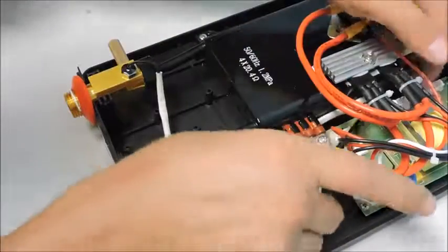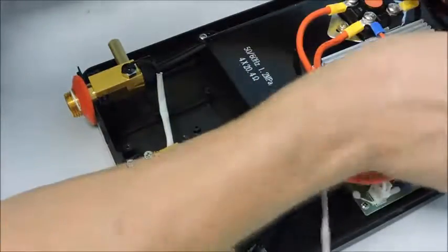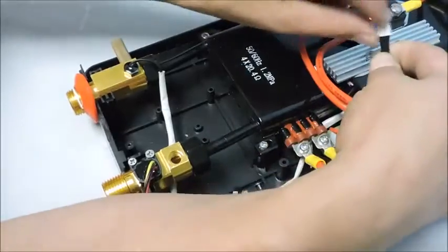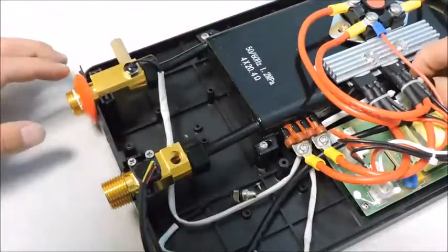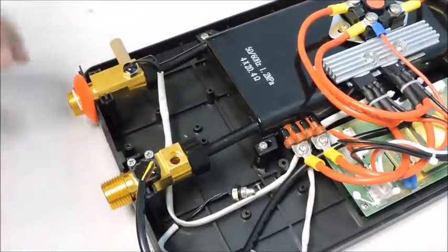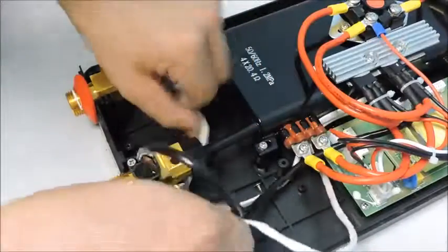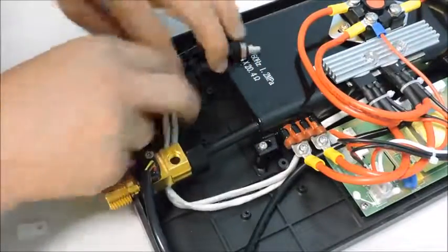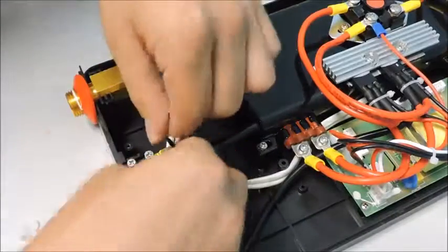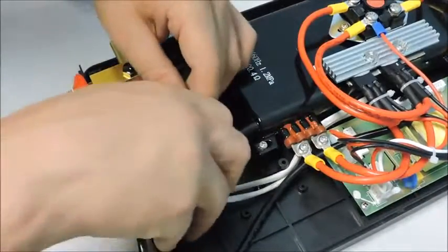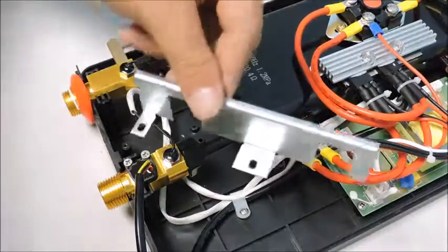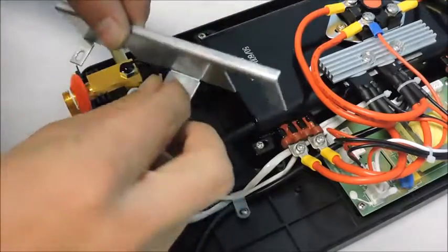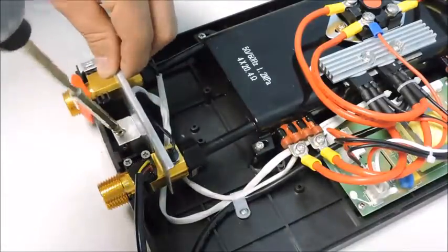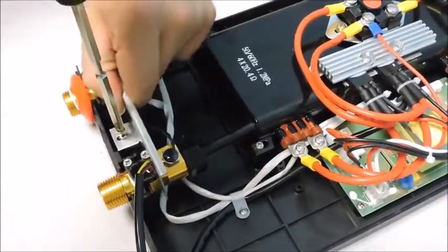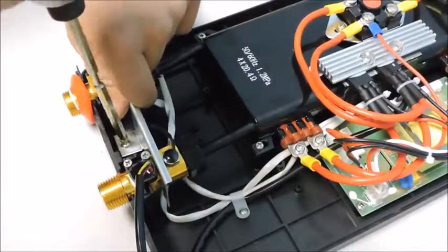Weave the new sensor under the power wires and plug back into the corresponding port. Be mindful that the plug clip can only be installed in one direction. Before reinstalling the inlet, twist the inlet temperature sensor wire counterclockwise about 3 times to prevent the wire from twisting when installing. To ease in the installation of the bracket, put the screw in the center hole before reinstalling the bracket. Make sure to install the second screw. This completes the basic troubleshooting and repair for the Marey ECO110.